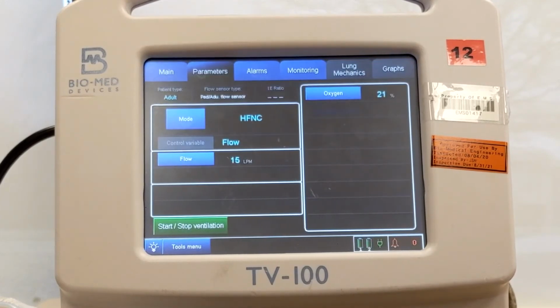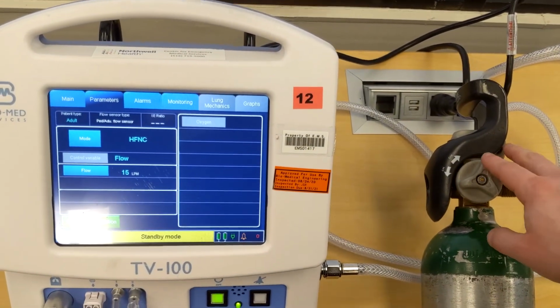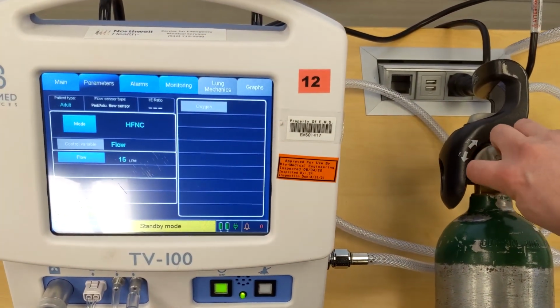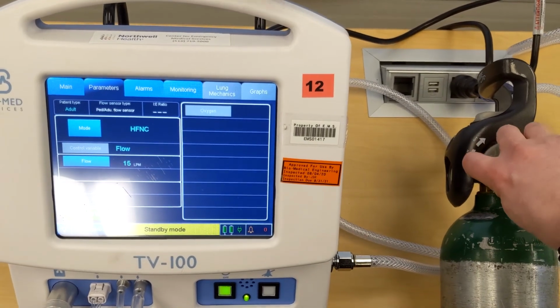In high-flow nasal cannula mode, there are only 2 variables you can change: the flow, which is in liters per minute, and FiO2, shown as oxygen percentage on the screen. If the system does not have oxygen inside it, the oxygen box will be grayed out, and you will not be able to adjust the FiO2.